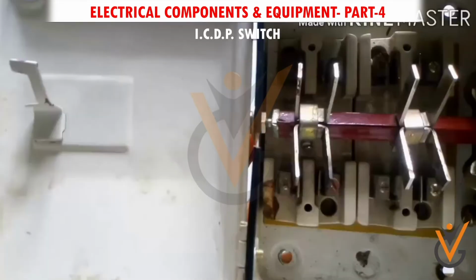ICDP switch. Iron-clad double-pole main switch is used in single-phase supply circuits. These are available in 15 amp, 30 amp, 60 amp and 100 ampere current ratings. In these switches, either 2 fuse links are provided or a fuse link and a neutral link. The neutral wire is directly connected with the neutral link and the phase wire is connected with the fuse link. Normally 15 amp current rating main switches are made of plastic molding instead of iron.